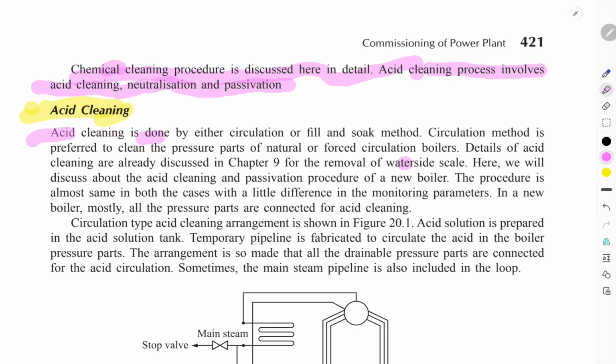Acid cleaning is done by either the circulation or the fill and soak method. The circulation method is preferred for cleaning the pressure parts of natural and forced circulation boilers. Details of acid cleaning are already discussed in chapter 9 on the removal of water side scale. Here we will discuss the acid cleaning and passivation procedure of a new boiler. The procedure is almost the same in both cases, the difference being in the monitoring parameters. In a new boiler, mostly all pressure parts are connected to the acid cleaning.